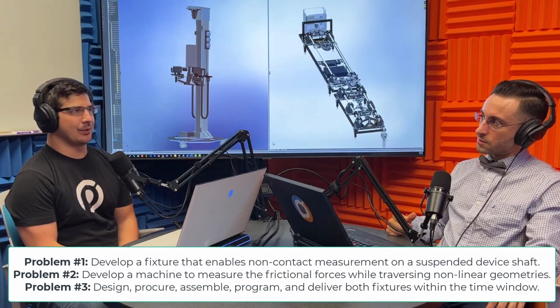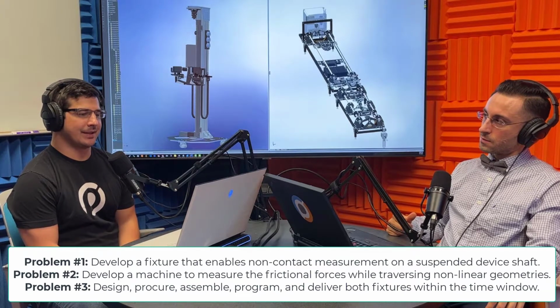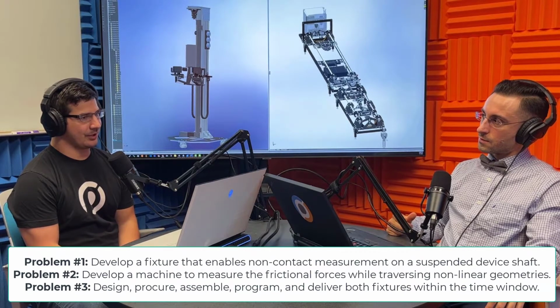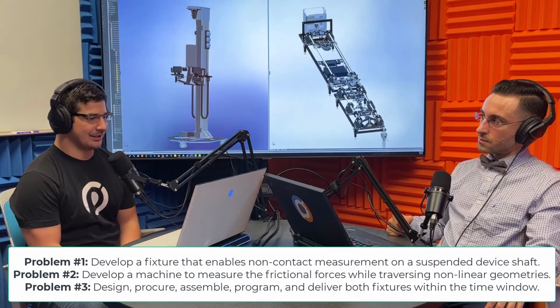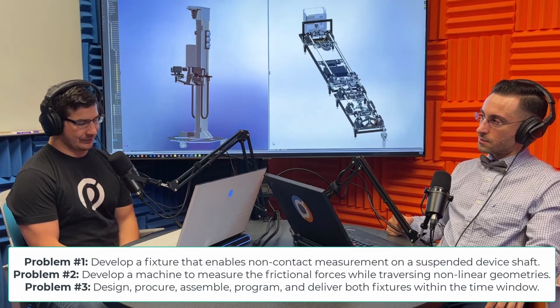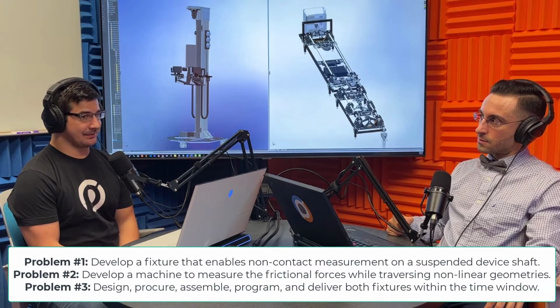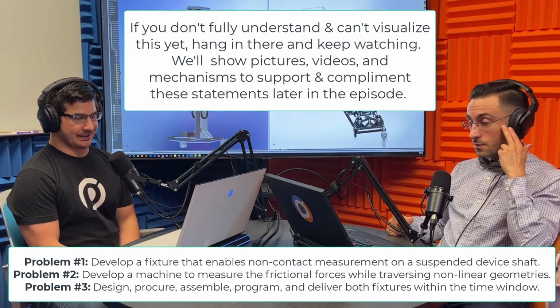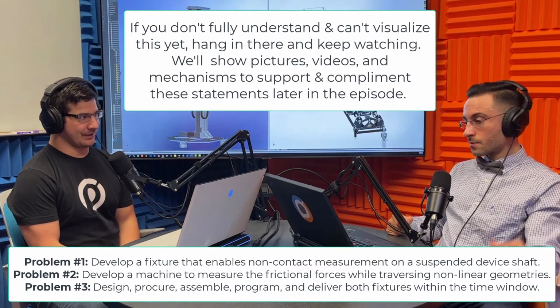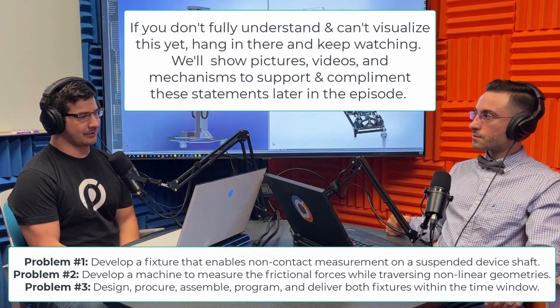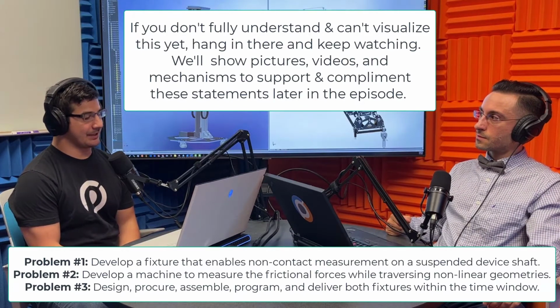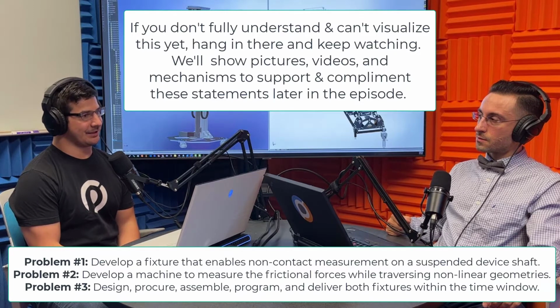From the customer standpoint, they need to know that their device and how they're developing it is going to perform as advertised. So one of these devices is what's called a catheter. It goes intravenously into the patient's body. Due to that, it can cause friction with the inner walls of the arteries. So we set up systems to measure that friction and make sure that the coating on the device is not causing any problems.